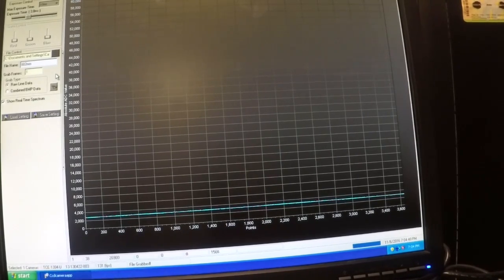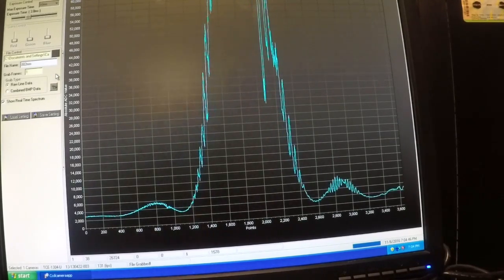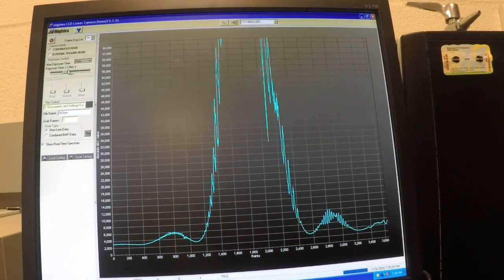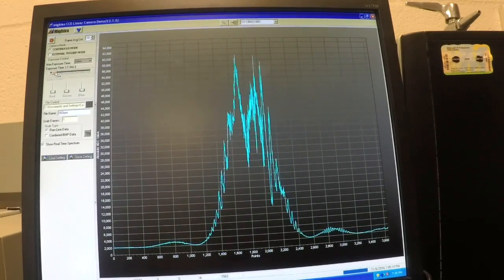You want to look on the back of this slit to make sure that your light is going through the slit, and you also are seeing on the screen when the light is going through the slit. So the one thing you have to do here is reduce the exposure time, because you need to make sure that the whole intensity profile is on the screen. These impurities here that you see, you should see the nice and straight line, but these are the actual interference from the microscope glass that's used to keep these slits together. And this is something that we cannot fix, so just keep ignoring it.